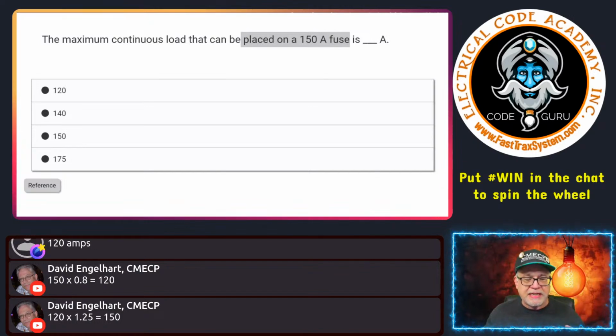So why is that a beautiful lesson? David, there you go on the screen, David sharing the process. If I already know what the load is, they tell me what the load is, and it's a continuous load. Again, if it's 39 amps of continuous load, what is the continuous load? It's not 39 times 125%. No, the continuous load is 39 amps. The reason we do it at 125% is for the wire sizing. The load is the load. You've heard me say that for decades. Load is the load. 39 amps, if it's a continuous load, it's the load.